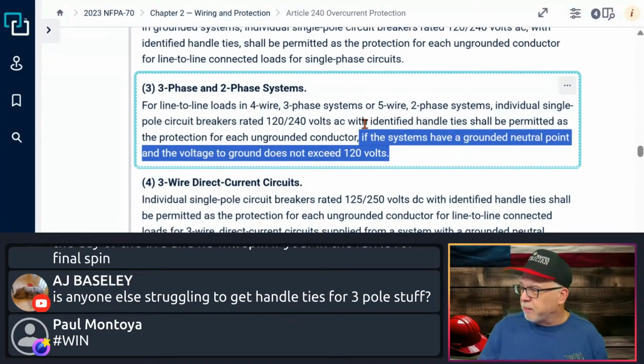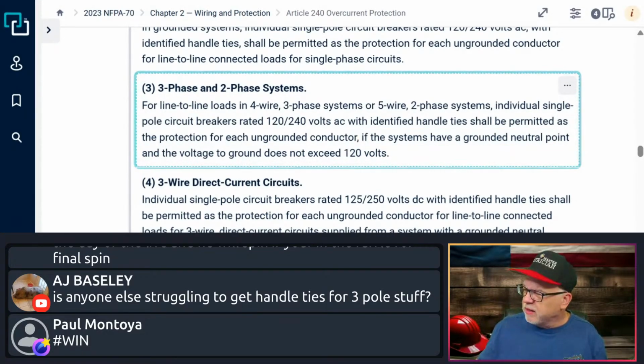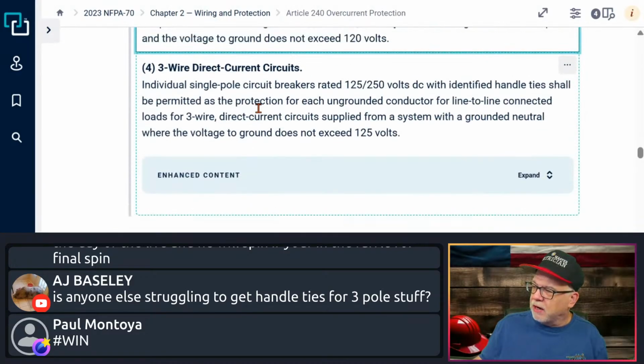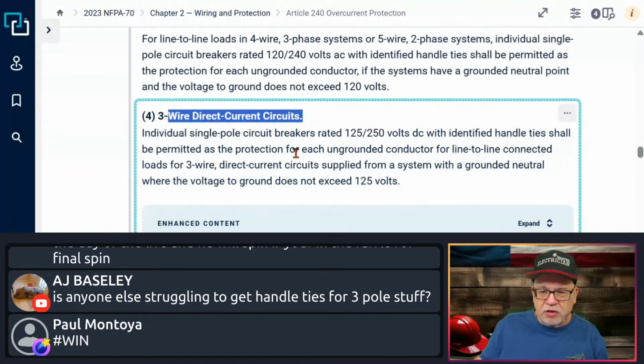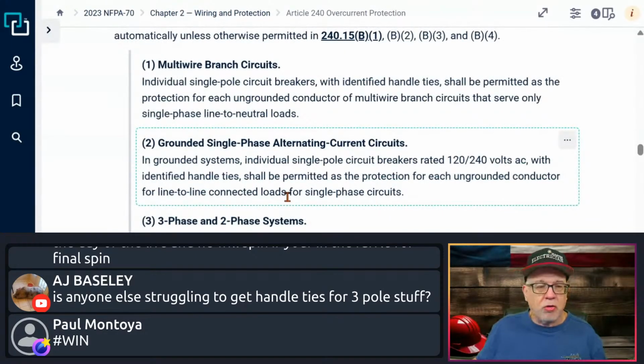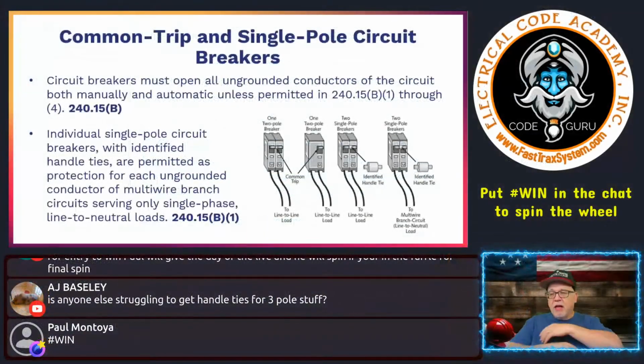So an example of this would be one of the systems where it's not being used on a delta high leg. Because one of those legs to ground would exceed 120, right? So it's not going to be used on a delta high leg system. It might be a Y system. The point being here is that in a three-phase system, I could use 3 individual circuit breakers with identified handle ties. It's going to work essentially the same thing. Not going to work when you have the delta. And then you've got here a 3-wire direct current circuit if you're dealing with direct current applications. So that's kind of covering when you can and can't. I think in most situations, taking the delta high legs out of it and buying those specific breakers, be careful.